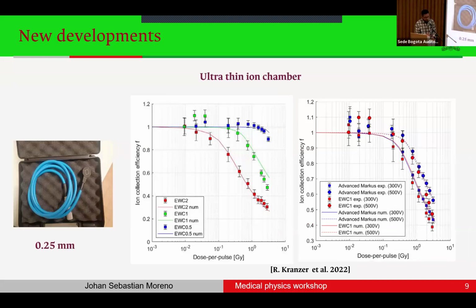And for the ultra-thin ionization chamber, the strategy was to decrease the spacing. They use a plane parallel ionization chamber. So if we decrease the spacing between the electrodes, we improve the ion collection efficiency. And also, we use it at a suitable high voltage, not too high because then we have charge multiplication. But that was the strategy, and we used this prototype where the spacing between the electrodes was 0.25 millimeters.